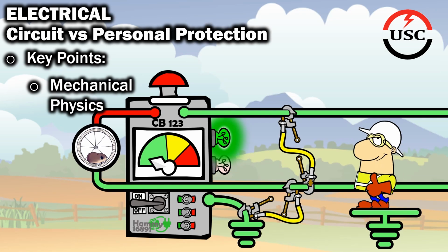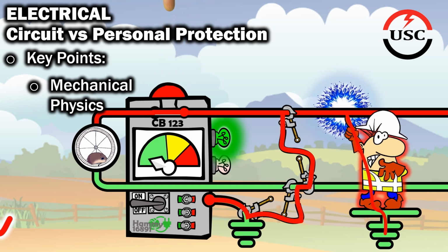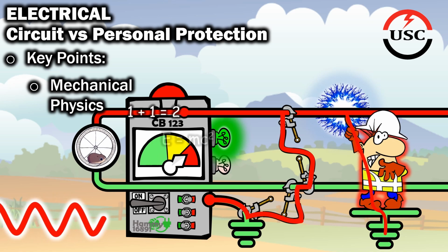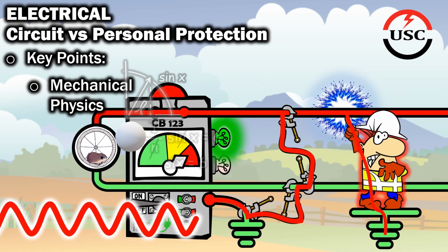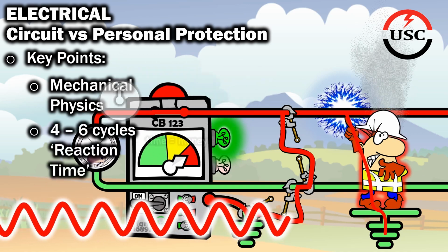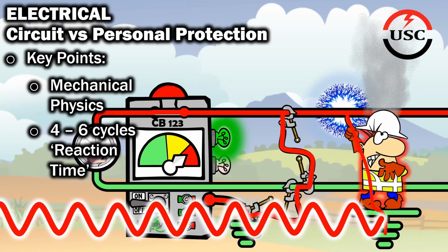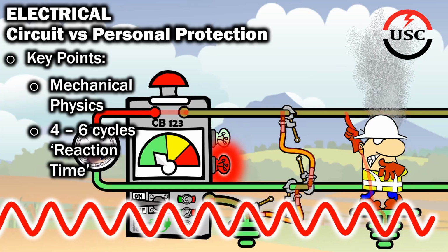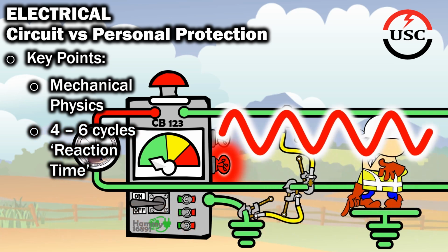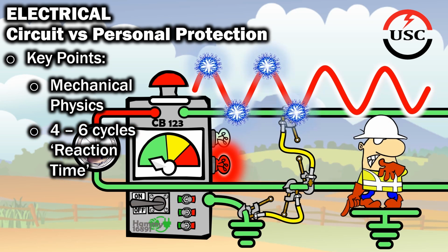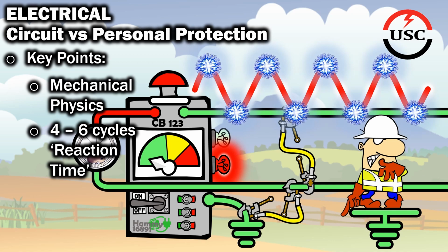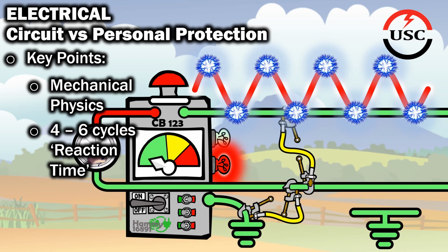Second is mechanical physics. Circuit protective devices, whether they be fuses, circuit reclosers, circuit breakers, whatnot, are limited by the laws of mechanical physics. This means that peak efficiency circuit protective devices will still take about 4 to 6 electrical cycles from the time of detecting the fault current to the time of actually operating and effectively de-energizing the circuit. Since it takes circuit protection around 4 to 6 cycles to operate, workers will still be exposed to those 4 to 6 full cycles of fault energy before that circuit protection has the ability to eliminate the electrical exposure. This is the key reason why fuses, circuit reclosers, and circuit breakers cannot be relied on to protect human life.